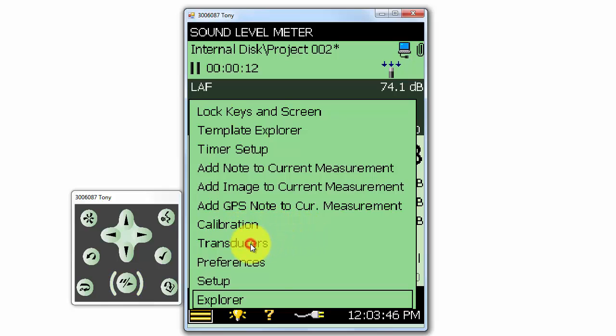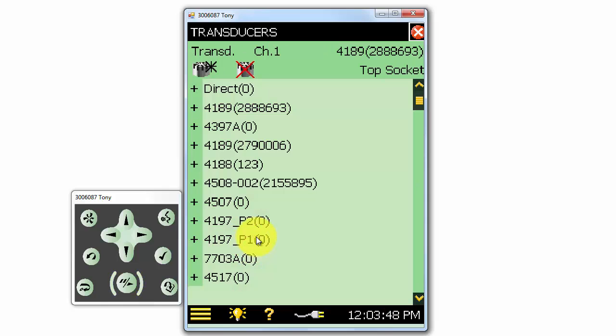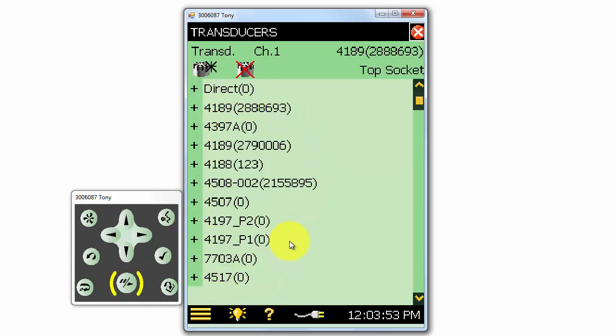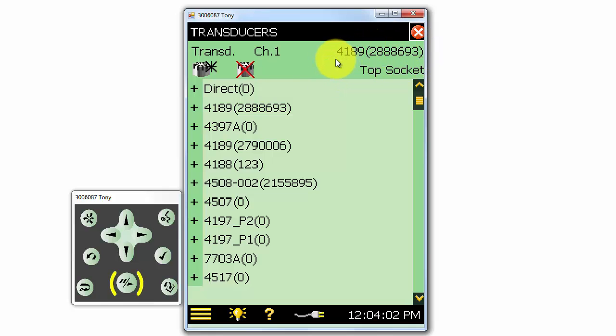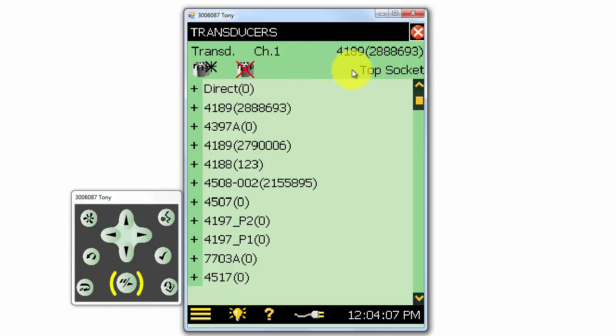The transducers list shows us the different types of transducers that have been added to the meter. The transducer that is currently selected is shown at the top right. The type of the transducer and its serial number are displayed. It also shows us that it is selected to be used in the top socket of the meter and as the channel 1 input. We'll take a look at how to create new transducers on the meter in another training video.